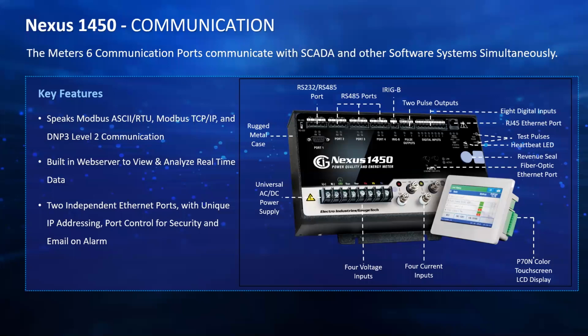So for example, you could have multiple entities within your organization talking to this meter at the same time. Maybe one entity, the billing department, is talking to the meter through MV90 through one of the ports, and then through a different port, the information is being sent to a third-party system. So you can do simultaneous communication over multiple ports on this meter. You can also choose to have 2 independent Ethernet ports with unique IP addressing. So you have your 2 ports, they have different Ethernet IP addresses, so different entities can be accessing the meter with their individual IP addresses without harming the security in any way.